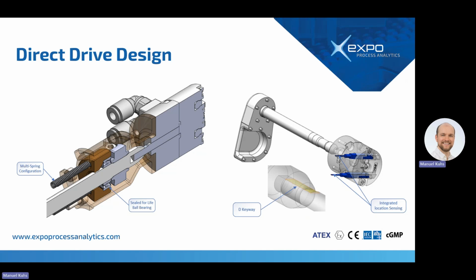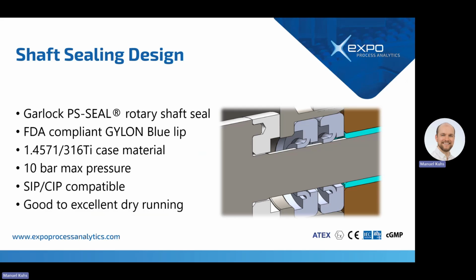The shaft sealing is another point. You'd get additional resistance and premature failures with some of the rotary O-rings, so they've been replaced with Garlock rotary shaft seals. Similarly to the legacy units, they're still supplied with all the material traceability certs and everything you'd expect, but we've just swapped them out for more suitable ones for the application.